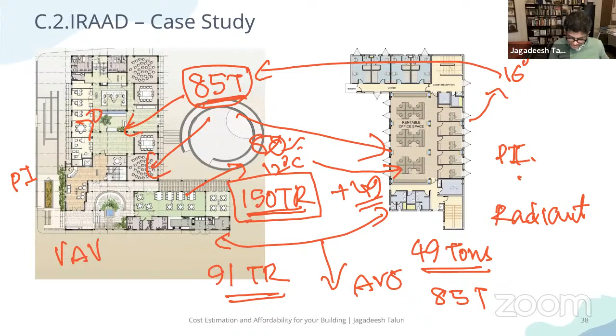The 85 ton chiller used to supply chilled water at 7 degrees to the phase one building. Whatever chilled water was coming out from the AHU was coming at 12 degrees. That 12 degrees centigrade water, they used to put into the radiant slab of phase two, which used to come out at, let's say, 16 degrees. Now this 16 degrees, they used to send back to the chiller and cool to 7 degrees. So that way they were able to multitask and come up with a system which was quite interesting. And so this is a smart sizing strategy.